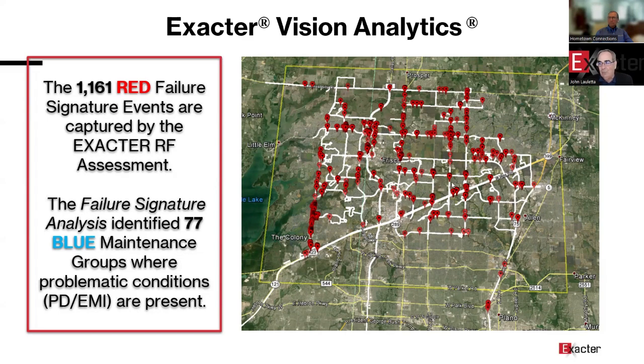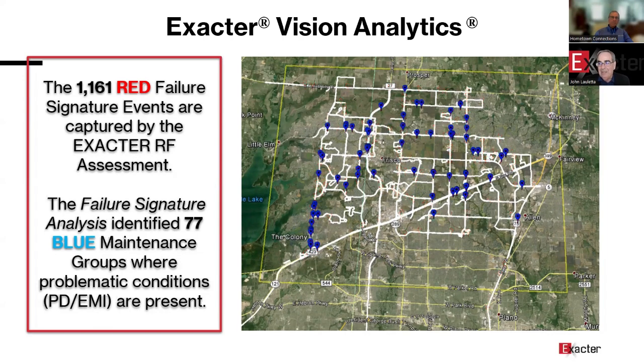So after we take the raw data from several passes of the grid, then we run it through our secondary process, which selects those key targets that you'll want to work on. And these are the blue dots. So that 1,100 number of readings turned into 77 important incipient failures that if you take care of, this grid will perform at a much higher performance level.